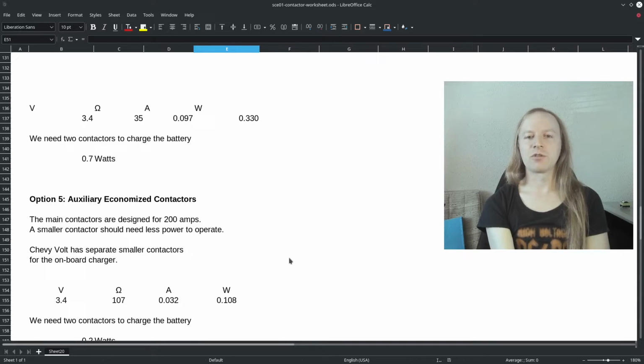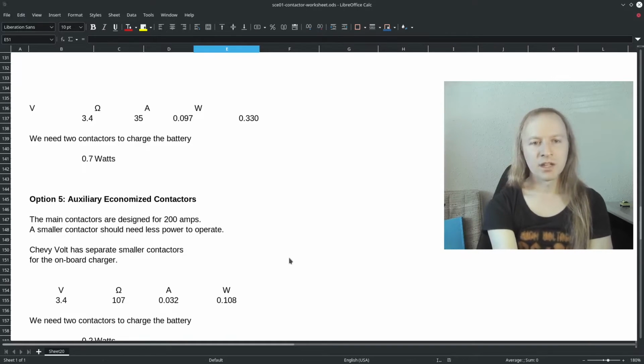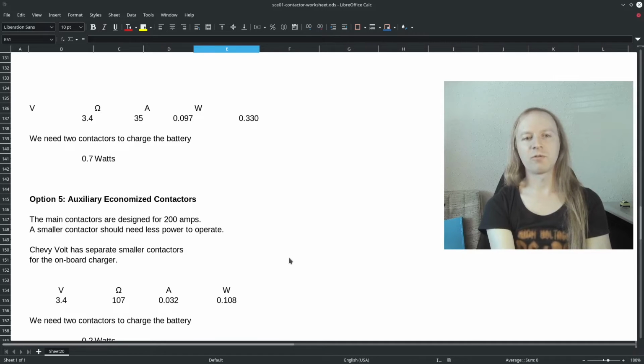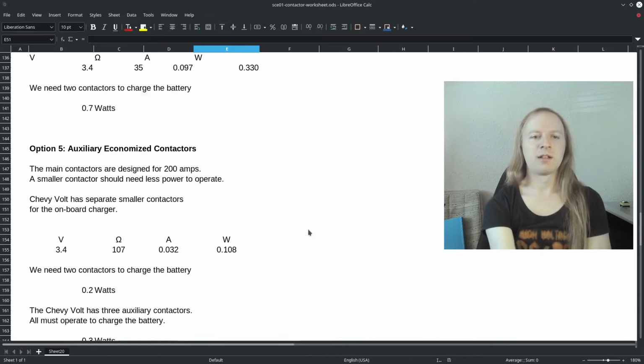These contactors have similar voltage requirements as the main ones, 12 volts nominal, but in practice can operate at much less. So here we could supply them with 3.4 volts. We found their resistance to be 107 ohms, calculating out to 0.032 amps, or 0.1 watts per contactor. With 2 of those contactors, it would require 0.2 watts.